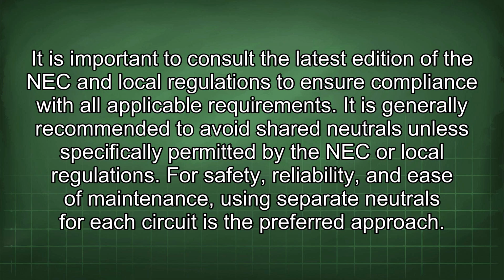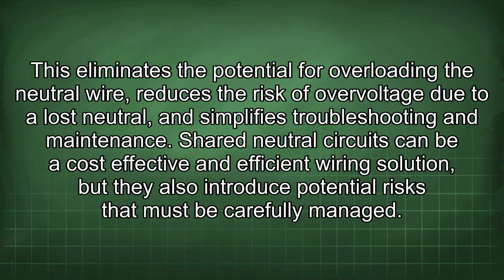It is generally recommended to avoid shared neutrals unless specifically permitted by the NEC or local regulations. For safety, reliability, and ease of maintenance, using separate neutrals for each circuit is the preferred approach. This eliminates the potential for overloading the neutral wire, reduces the risk of overvoltage due to a lost neutral, and simplifies troubleshooting and maintenance. Shared neutral circuits can be a cost-effective and efficient wiring solution, but they also introduce potential risks that must be carefully managed.